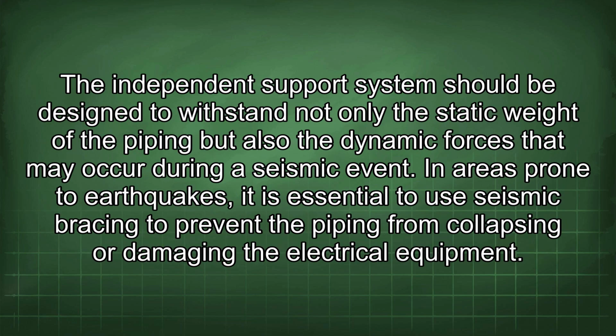The independent support system should be designed to withstand not only the static weight of the piping but also the dynamic forces that may occur during a seismic event. In areas prone to earthquakes, it is essential to use seismic bracing to prevent piping from collapsing or damaging the electrical equipment.